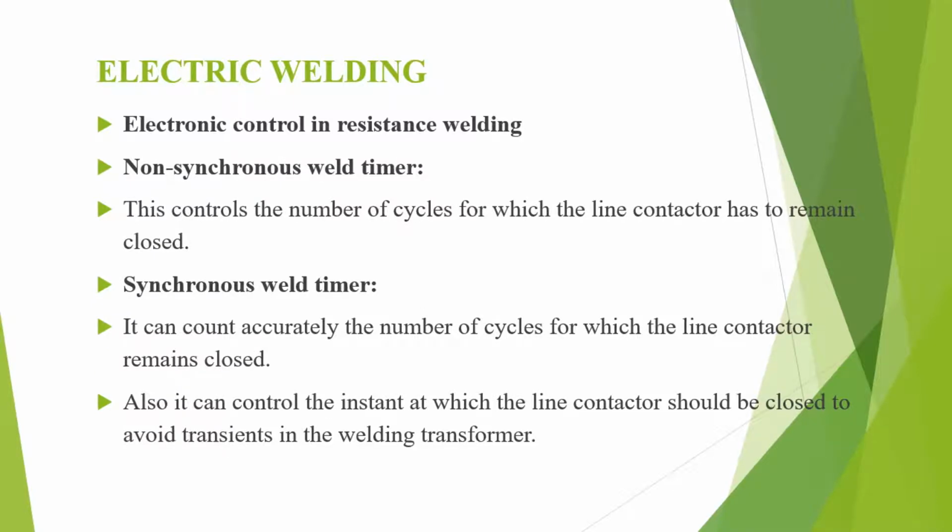Non-synchronous weld timer. This controls the number of cycles for which the line contactor has to remain closed. Synchronous weld timer. It can count accurately the number of cycles for which the line contactor remains closed.